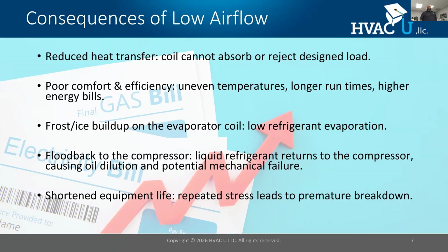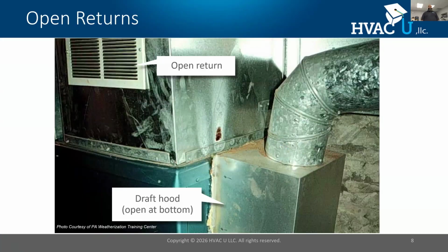What happens when you have an unreconciled duct system to equipment is that customers are going to be uncomfortable. They're going to respond and take action. And when they do, it's actually going to make the problem worse, not better. So we're going to talk about that. In extreme cases, we can get frost buildup on the evaporator coil if we're in the air conditioning mode, and we can flood back to the compressor, we can damage that, and we can shorten the life of those components. And oftentimes, in the heating mode, we run into cracked heat exchangers. This is a picture where a technician cut a hole inside the return air to alleviate some high temperature limit problems.